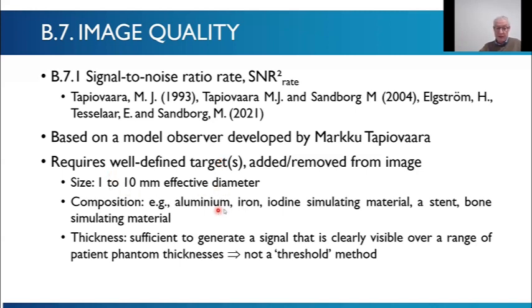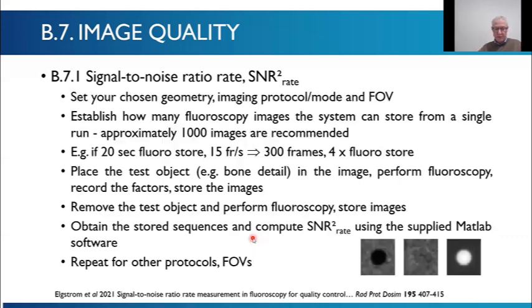It can be aluminium or iron or bone-simulating material. And it's not a threshold method. So you have something that's quite clearly visible over a range of phantom thicknesses, not too visible, but clearly visible. So you select the geometry that you want to evaluate, your protocol, your field of view. You need to establish how many fluoroscopy images you can store from a single run, because you do fluoro and then you store the images.